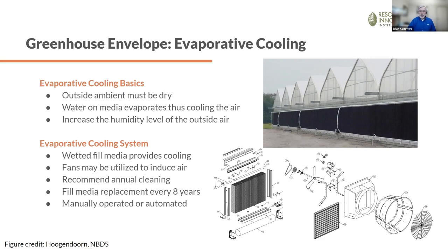I might take a little exception to that, particularly in areas where you have very hard water. There is a mineral buildup on this media, particularly calcium carbonate, and that needs to be removed, or you start losing the effectiveness of that evaporation. And these again can be manually operated or automated to turn on when you need that evaporative cooling effect.